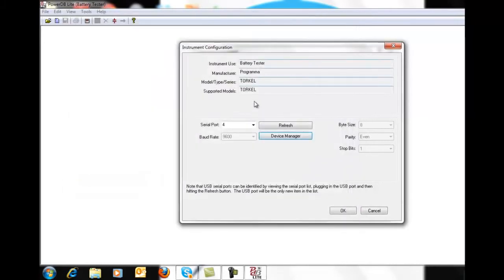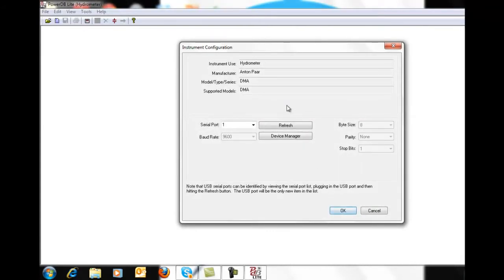So going back to our screen, we select port 4 for the TORKEL and hit OK, then select port 14 for the battery voltage monitors and hit OK. Now it also asks if I'm using a hydrometer. Today we're testing sealed cell batteries, so there'd be no way to take a hydrometer reading. As long as we don't have a conflicting serial port assigned, we can just ignore this and hit OK.